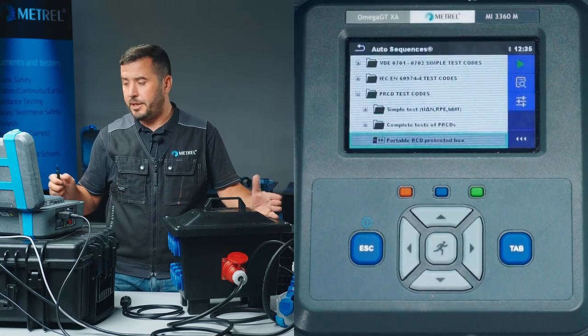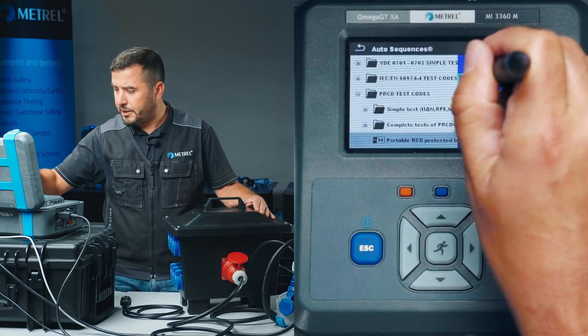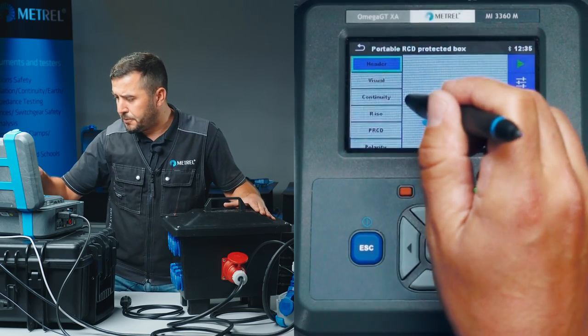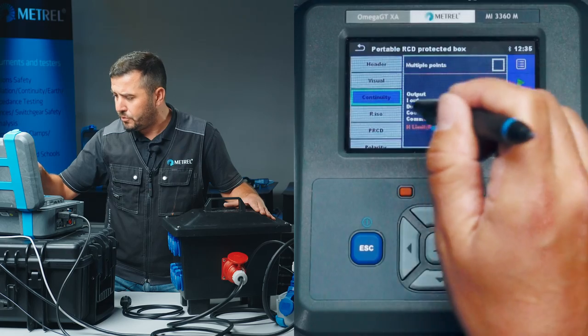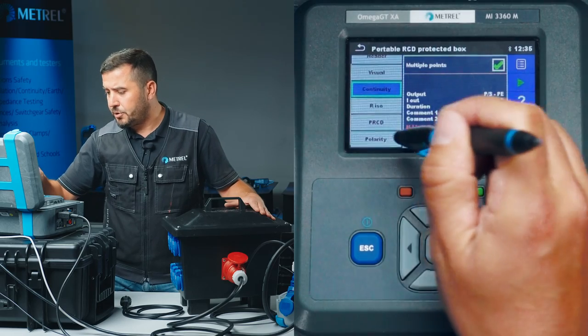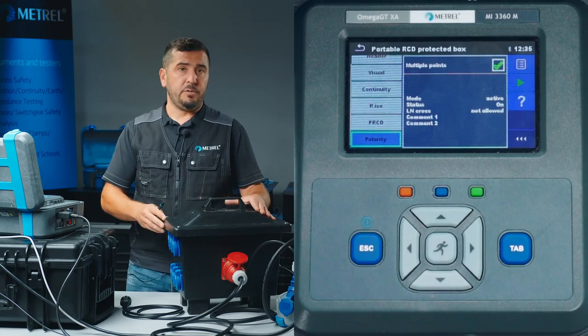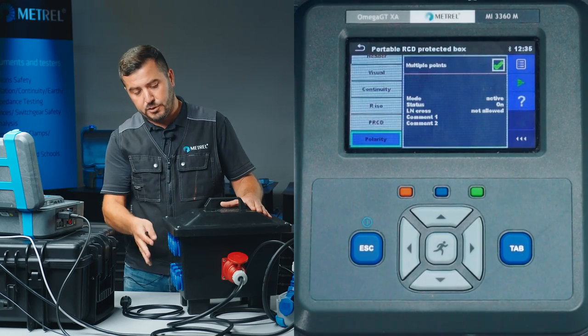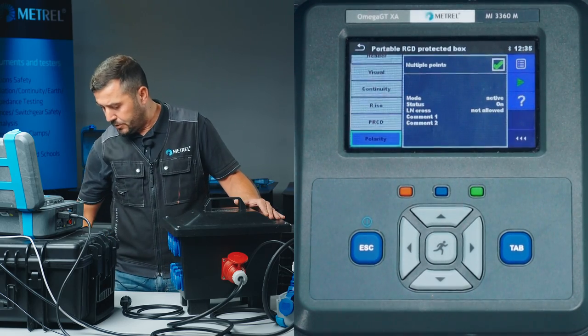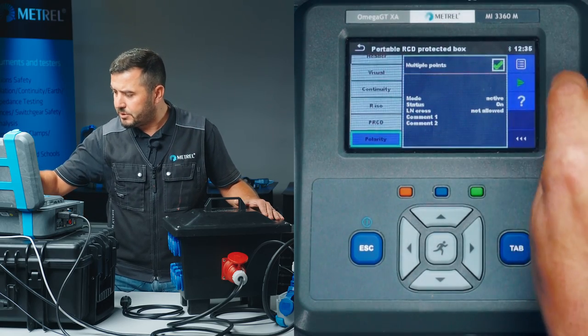Before we proceed with the actual testing, we will adjust a few parameters. We select the menu option 'Visual', and inside here for the measurement of earth continuity we select 'Multiple Points', and also for the measurement of polarity we again select 'Multiple Point Testing'. We have to do this because for earth continuity and polarity test all socket outlets have to be evaluated equally. After these two adjustments are made, we simply start with testing.